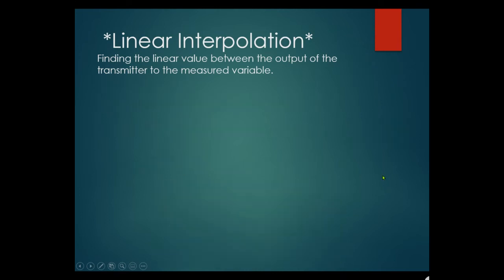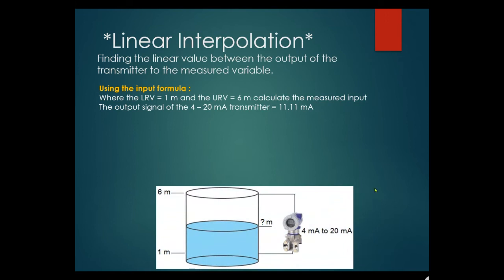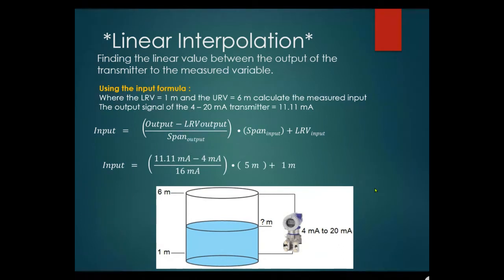For the input formula example: lower range value is 1 meter, upper range value is 6 meters, but this time the output is 11.11 milliamps — what is the input? Using the input formula: 11.11 milliamps minus 4 milliamps LRV, divided by the span of 16, times 5 meters, plus 1 meter. We get 3.22 meters.